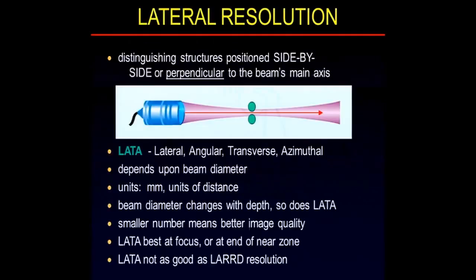The next resolution is lateral resolution. Lateral resolution distinguishes structures that are side by side or perpendicular to the beam's main axis. And it depends upon beam diameter. And a beam looks like an hourglass. So since beam diameter changes with depth, lateral resolution changes with depth. Where is it the best? Where the beam is the narrowest. That's called the focus. Okay? That's called a focus.